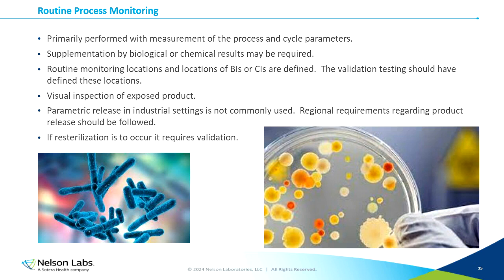So routine monitoring locations and locations of BIs and CIs are defined. The validation testing should have defined those locations. So we want to make sure that we have defined those locations where we're going to either perform routine monitoring or we're going to place our BIs and CIs. Oftentimes, visual inspection of exposed product may occur during routine, when we're releasing from the process. Parametric release in industrial settings is not commonly used at this point in time. And as mentioned, regional requirements regarding product release should be followed.